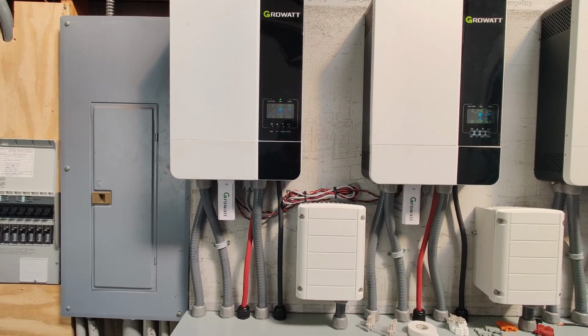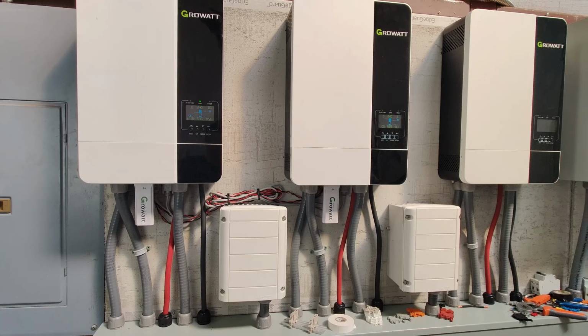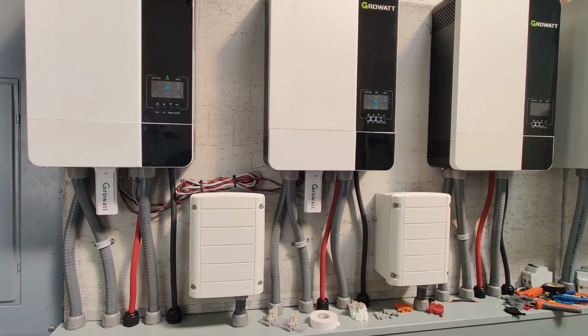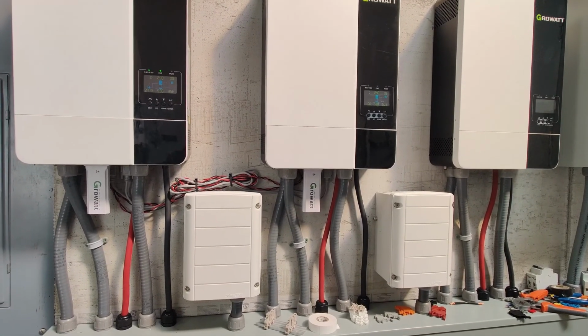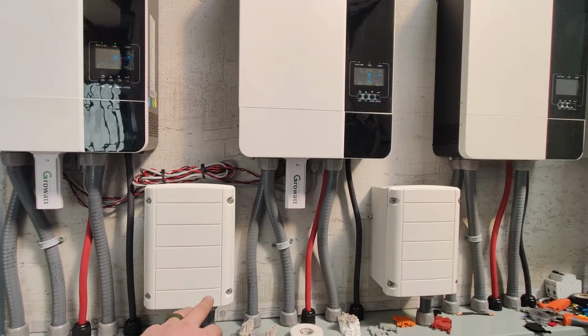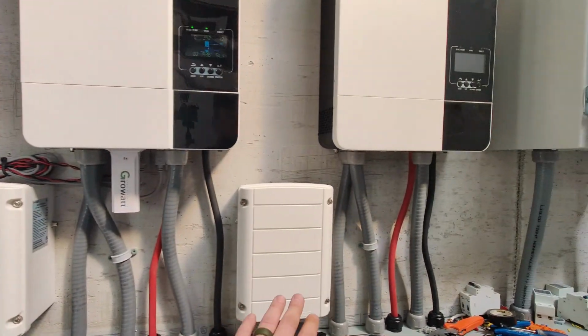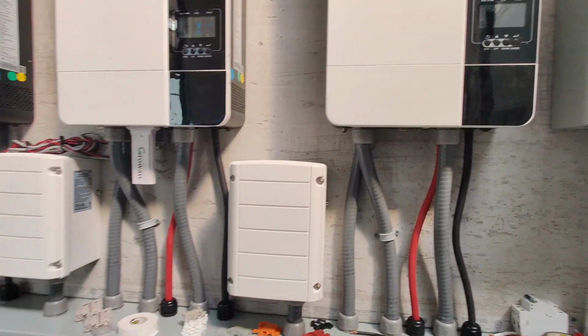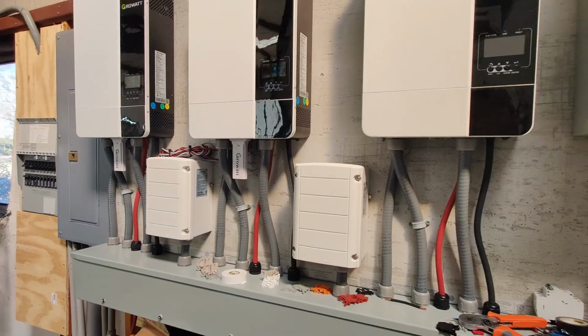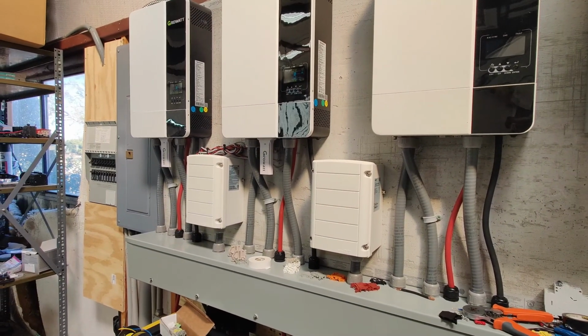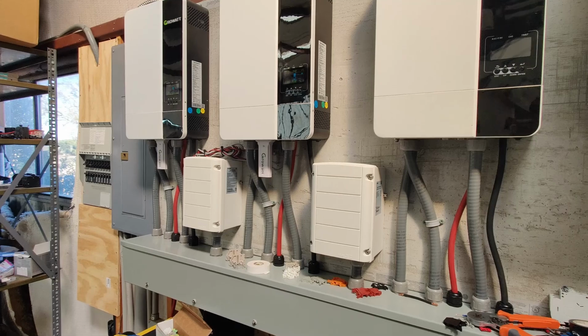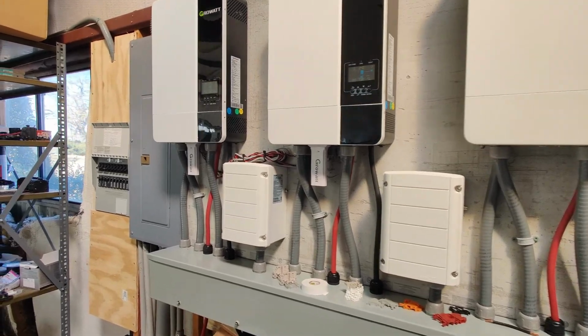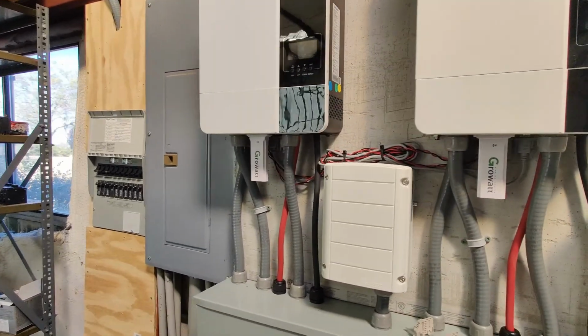So we wanted to put together a safer way to set this up, and also get some monitoring in on the auto transformers. The next thing we're going to be doing is hooking up some heat monitoring to those auto transformers, so we can also kill the system when the auto transformers overheat.